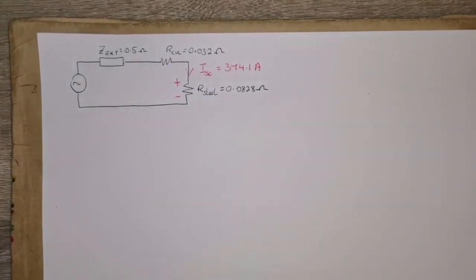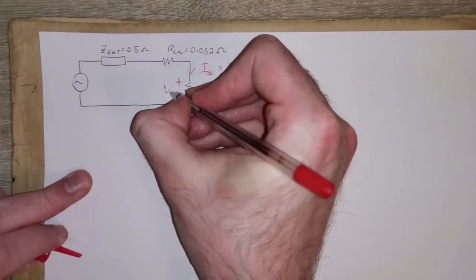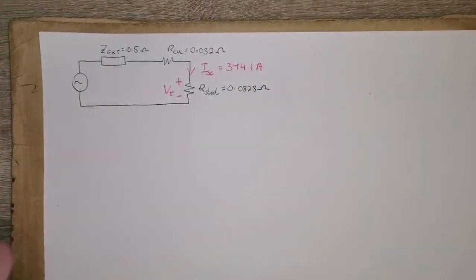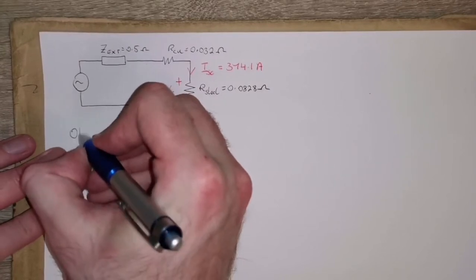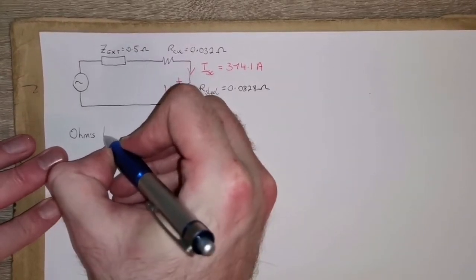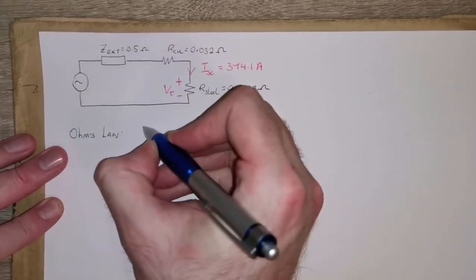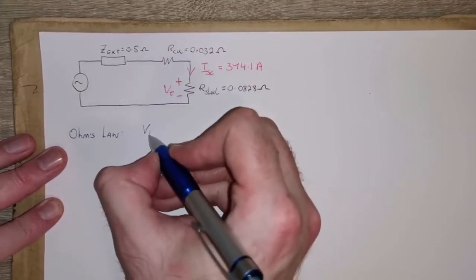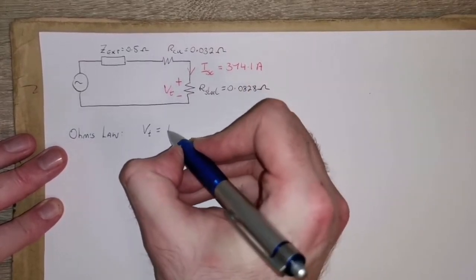We'll call it Vt, voltage for touch voltage. So again, just with Ohm's law, we can work out that the touch voltage is going to be the short circuit current multiplied by the resistance of the circuit protective conductor, which is the steel in this case.